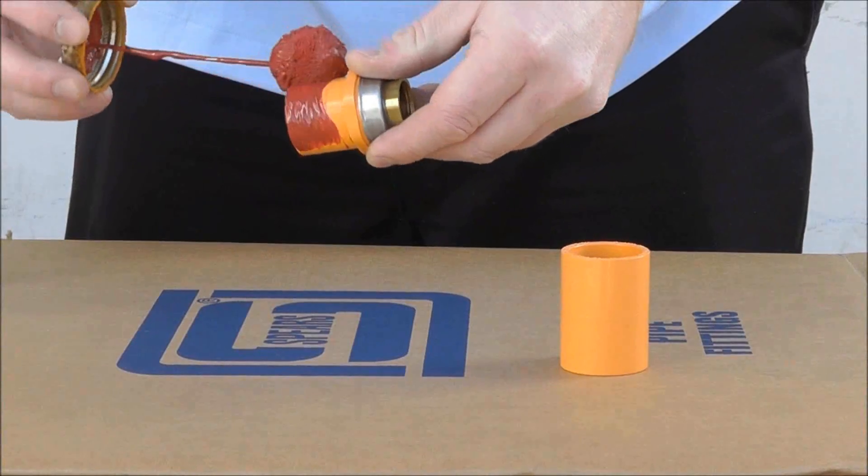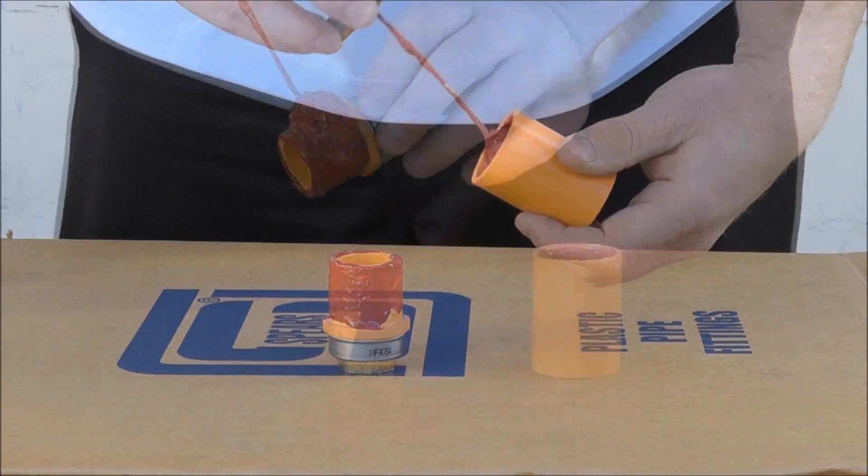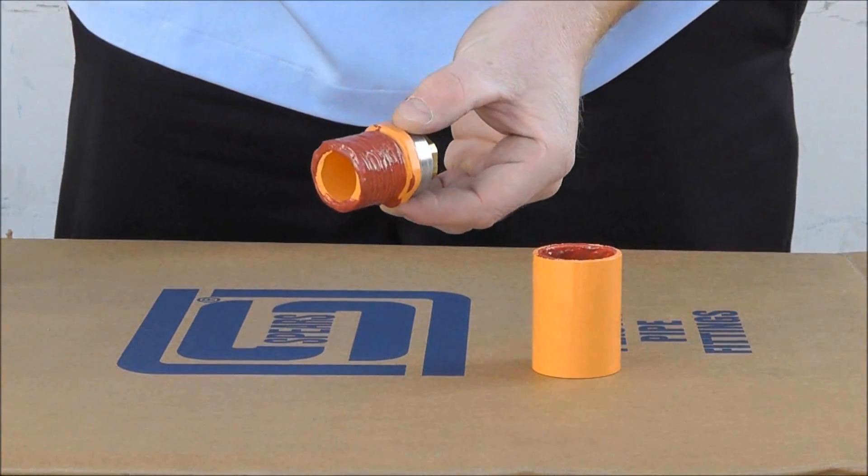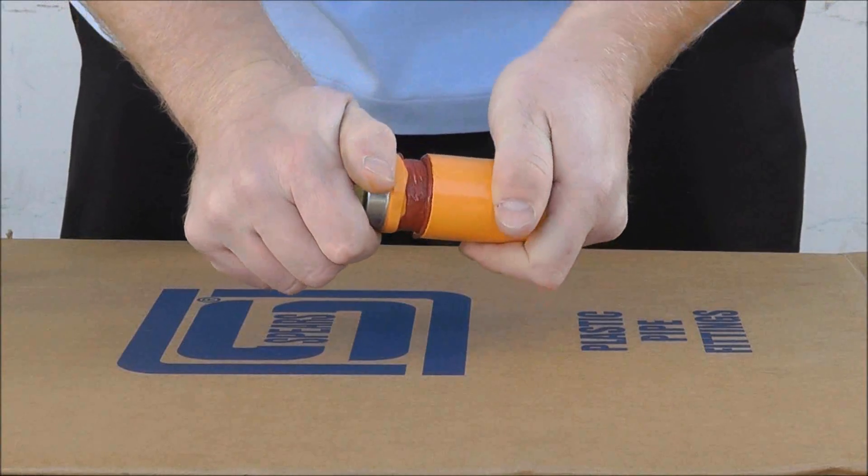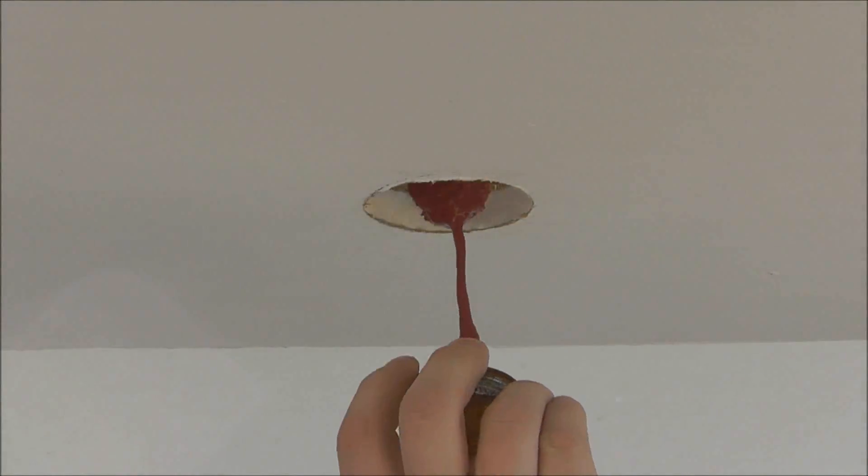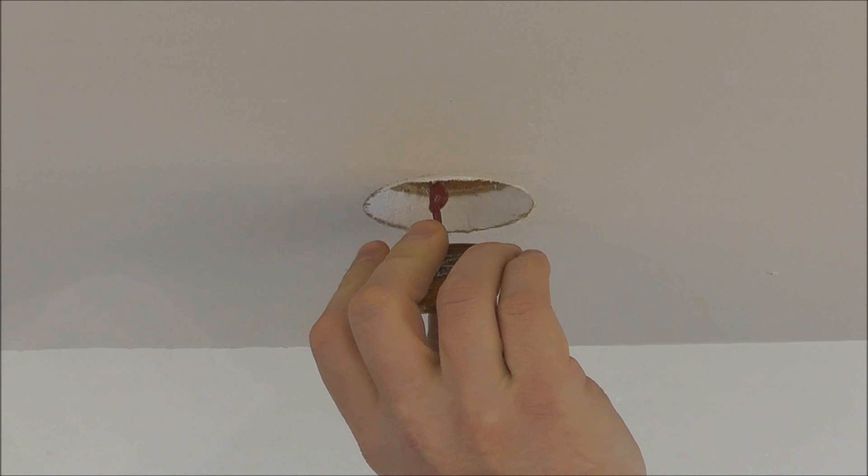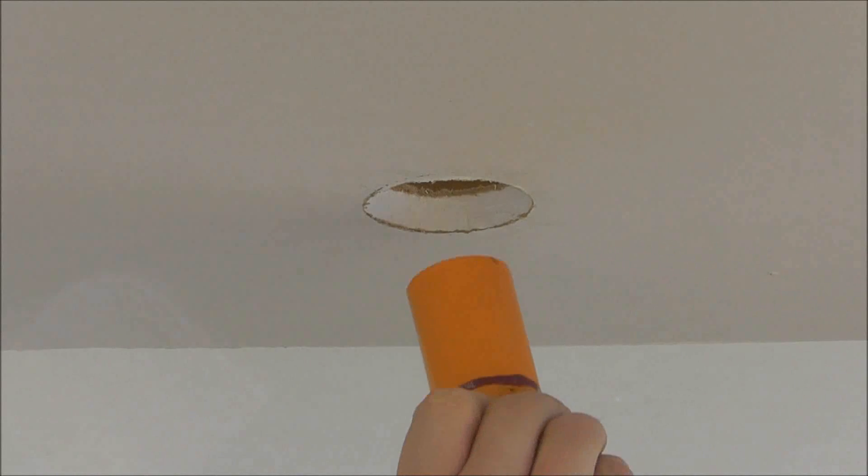Now using the Spears FS-5 solvent cement, cement the coupling and the spigot head adapter together. Make sure the fire sprinkler drop is clean then apply solvent cement. Also apply solvent cement to the 1 inch coupling and then attach the coupling to the fire sprinkler drop.